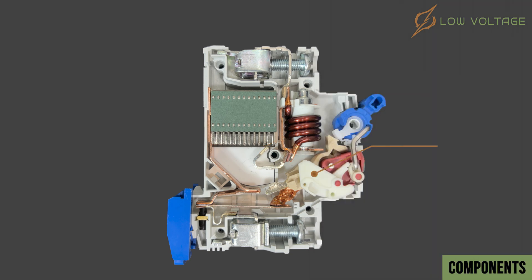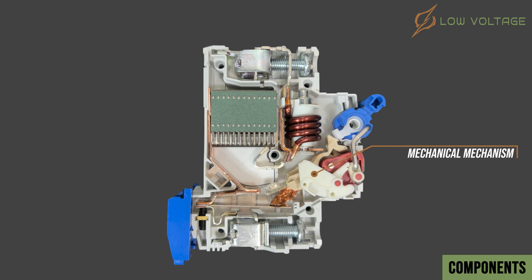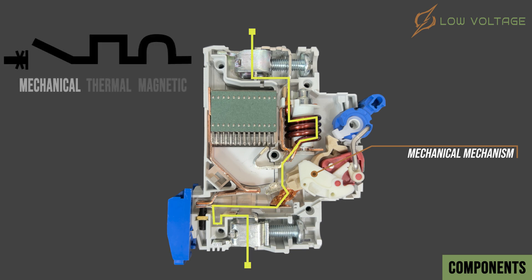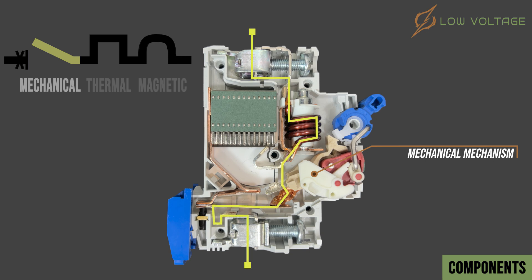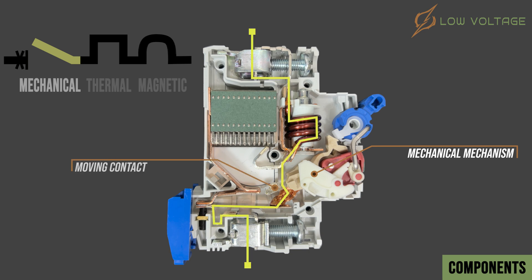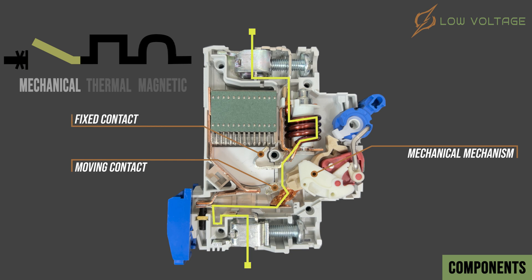Thermal and magnetic units are connected with each other in series to complete the protection circuit through a mechanical mechanism, described with this symbol in electrical drawings. This is achieved by a moving contact in connection with the thermal unit and a fixed contact in connection with the magnetic unit.